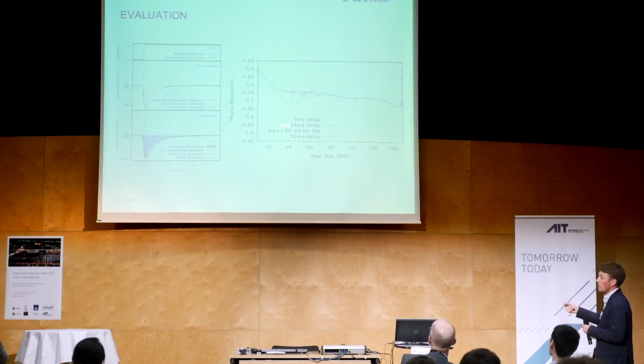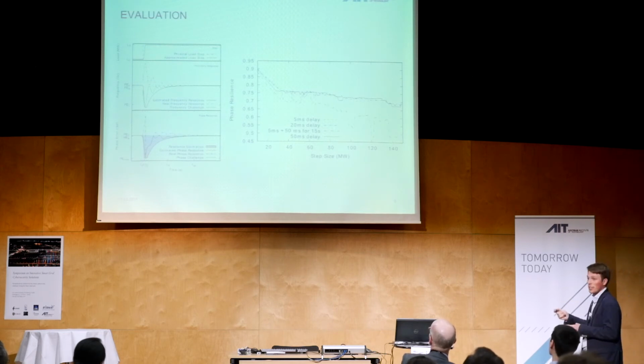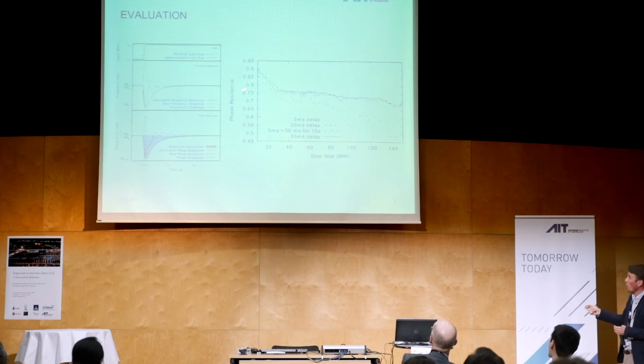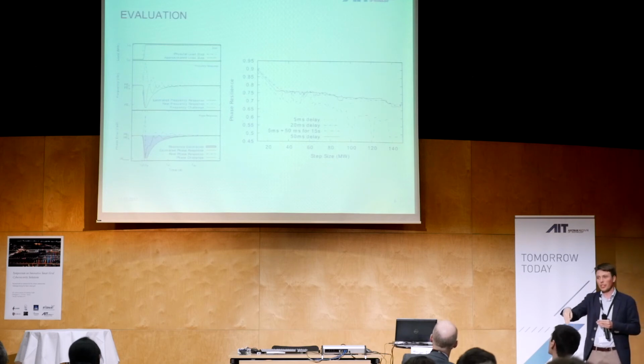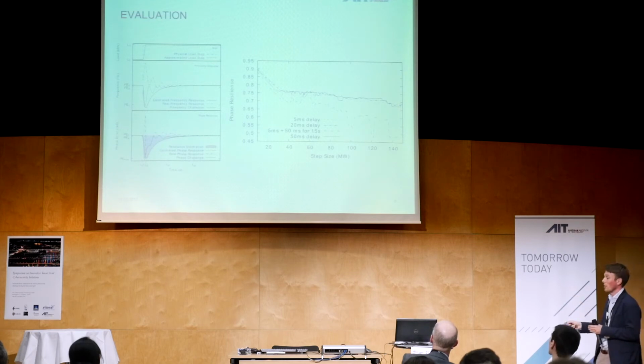And then we introduce different network delays in our system, also just to see how the response is to different network delays. And this is quite interesting because in the beginning, if we have a small load step, we see our recovery potential. Because with the small load step, the frequency is not changing that much, and that's why the phase error is not big enough to hit its maximum. And that's why this is more or less a linear degradation. So at some point, we reach a linear degradation, and then we hit this point where our recovery potential, or absorbing potential, is used up. And then only the recovery potential counts. And this is more or less static.